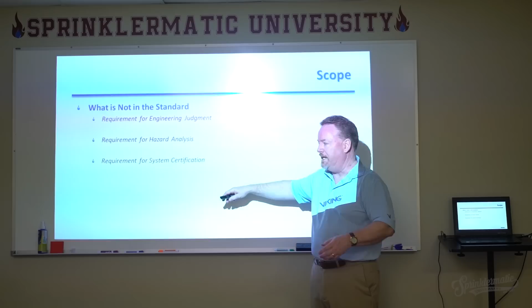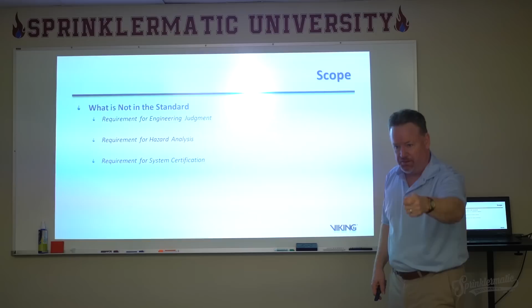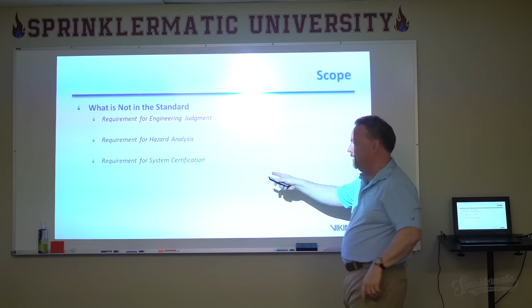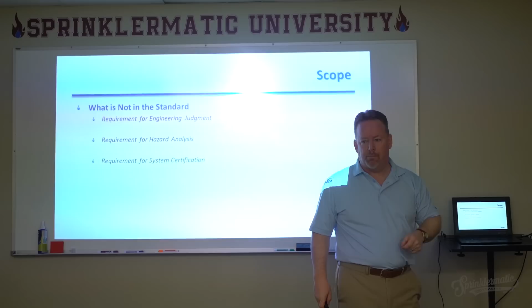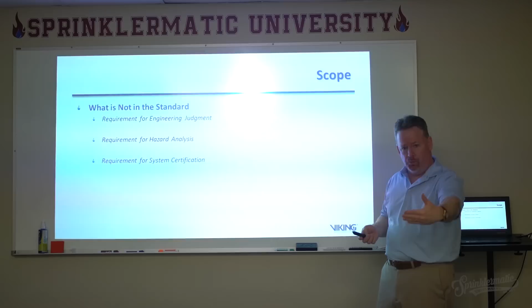The requirement for hazard analysis isn't there—whether a room is light hazard or ordinary hazard. Regardless of what you think, when you're handing in your report or green-tagging a sprinkler system, you're not doing system certification. You're simply doing a status tag: this is the status of the system I found, and it appears to be in good condition—everything appears to be in good condition. But you're not certifying the system itself; you're just saying it looks like it's in good shape. Whether it will actually do what we want was already established by the installation standard and certified when the building was given a CO.